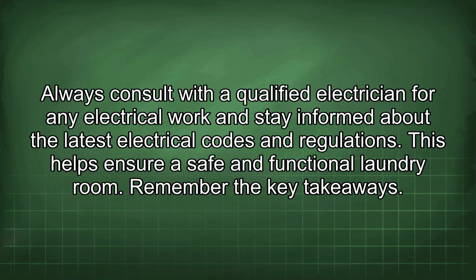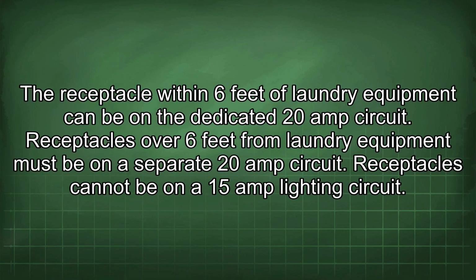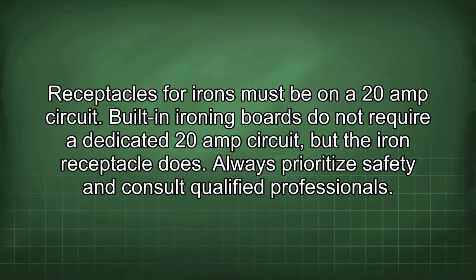Remember the key takeaways. The receptacle within 6 feet of laundry equipment can be on a dedicated 20-amp circuit. Receptacles over 6 feet from laundry equipment must be on a separate 20-amp circuit. Receptacles cannot be on a 15-amp lighting circuit. Receptacles for irons must be on a 20-amp circuit. Built-in ironing boards do not require a dedicated 20-amp circuit, but the iron receptacle does. Always prioritize safety and consult qualified professionals.